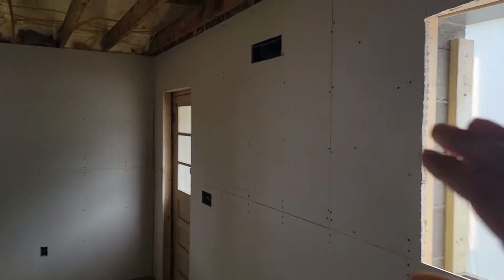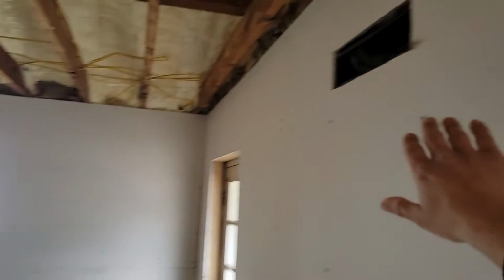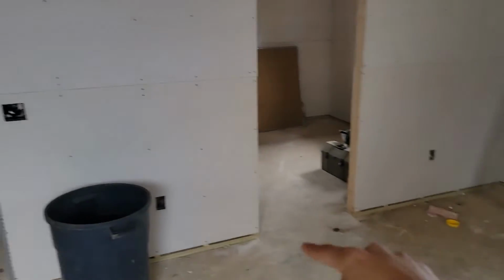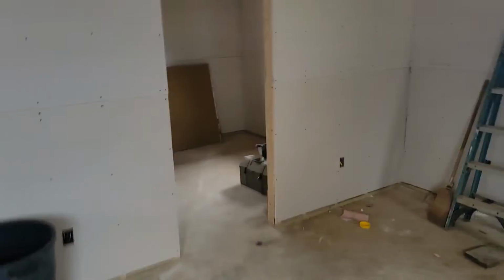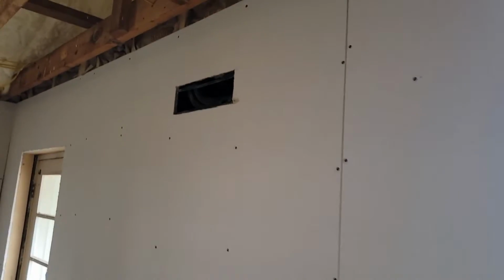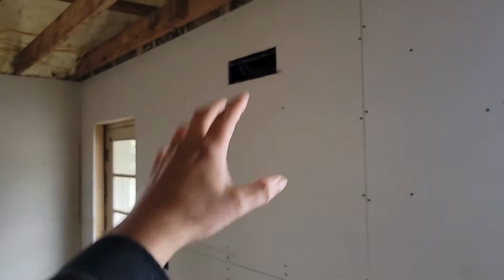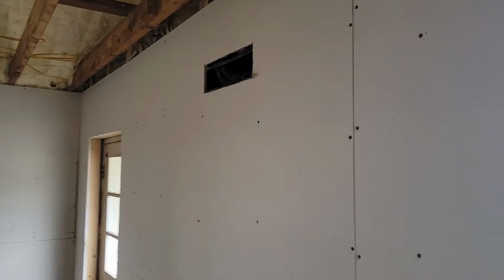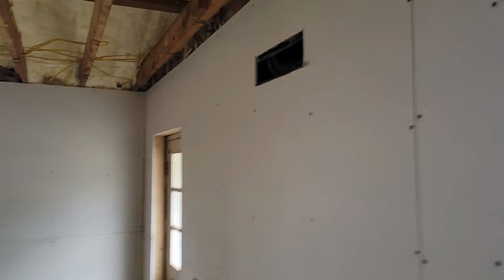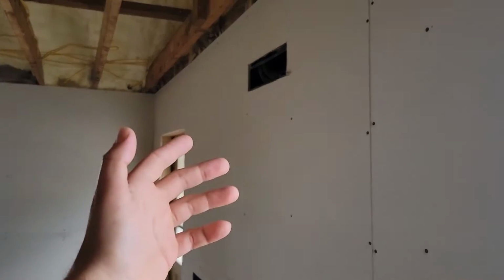Now I'm going to talk to you about what happens if you oversize the equipment. Say I take, and instead of installing a 1-ton wall mount air handler here that blows about 15 foot, which 15 foot would be halfway into that bedroom right there, say I installed a 3-ton unit. A 3-ton does about 2,000 square foot. I installed it there and it blows around 30 or 40 feet. What happens when the air circulates back into that air handler? Well, it short cycles. It shuts the equipment off before it should shut off. It shuts it off too often. It doesn't run enough. That affects the efficiency of the equipment and the longevity of the equipment.